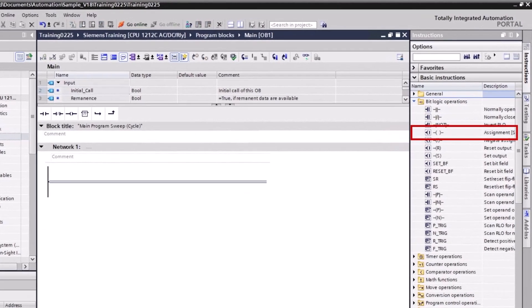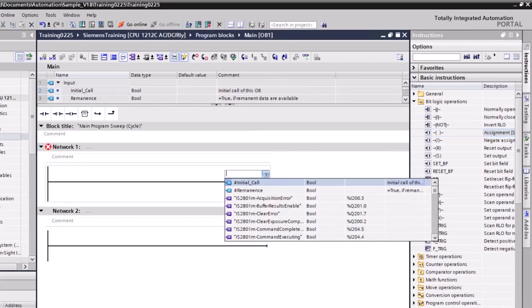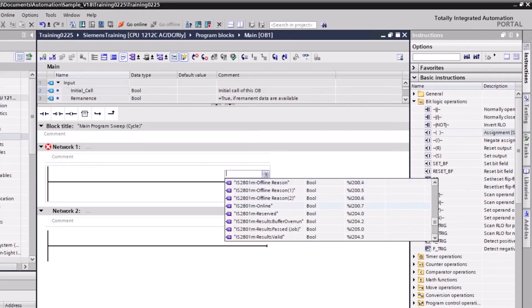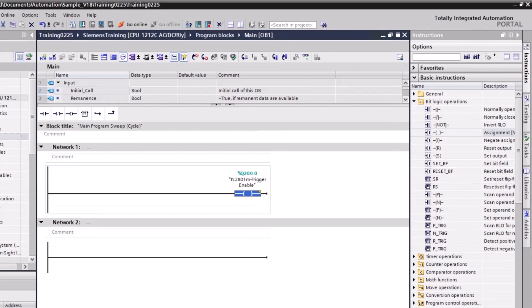Double-click the assignment instruction to add it to the first rung. Double-click the question mark to open the drop-down list and select Trigger Enable from the list. Press the Enter key to add the instruction to the rung. Setting this signal allows the vision system to accept triggers from the PLC, and the vision system will respond by setting the trigger-ready status signal high when the vision system is in the online state.